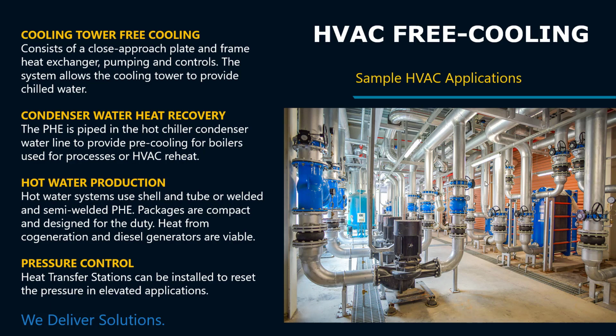Another approach is hot water production. Hot water systems use shell and tube or welded and semi-welded plate heat exchangers. Packages are compact and designed for the duty at hand. Heat from cogeneration and diesel generators are viable sources for hot water production using a free cooling heat transfer skid.